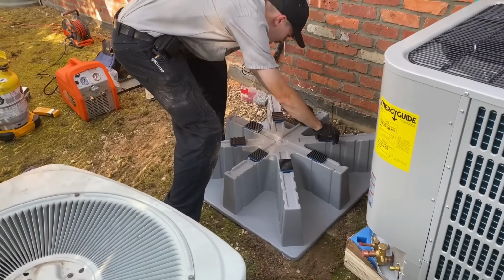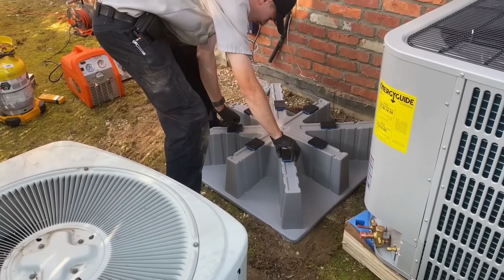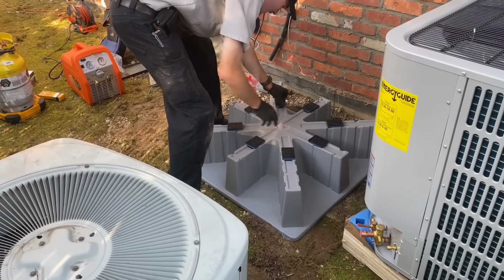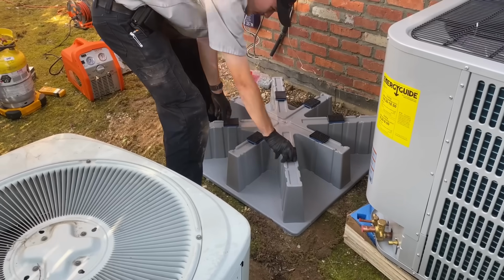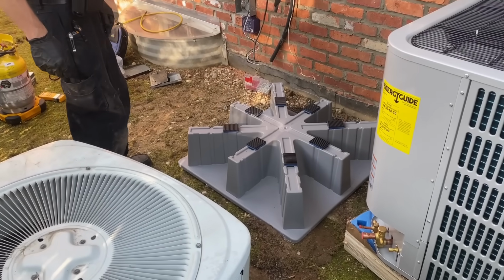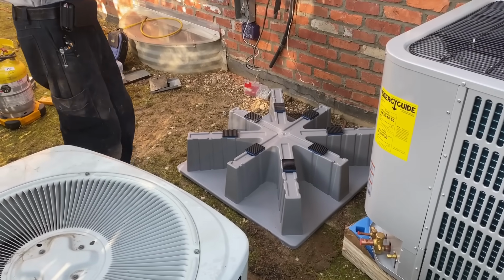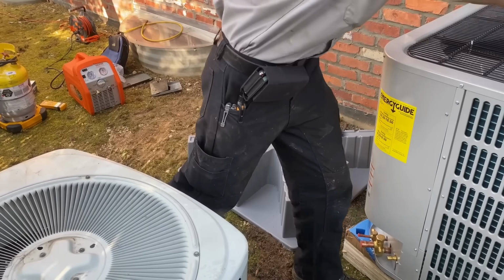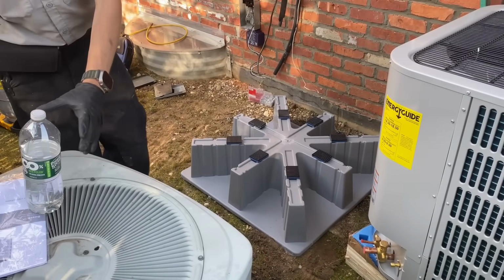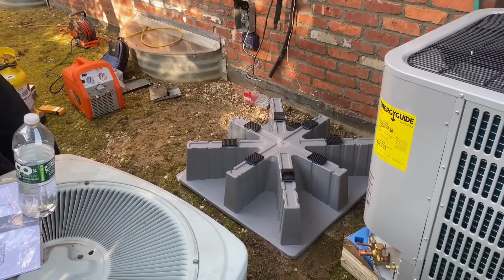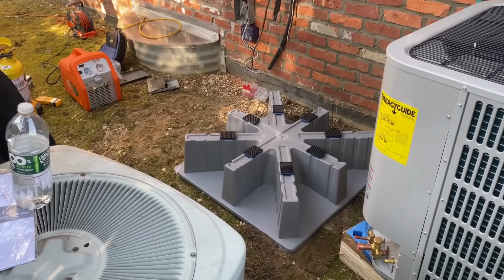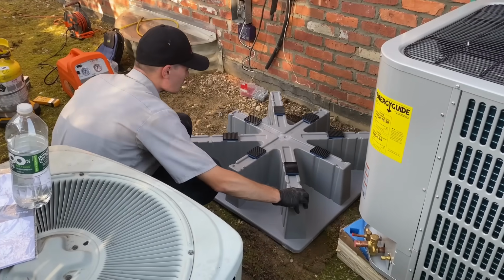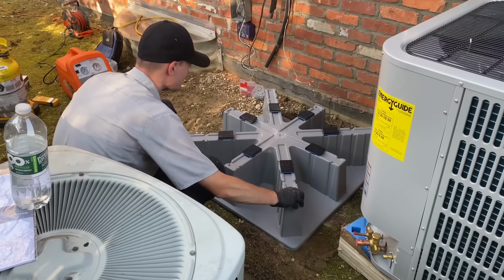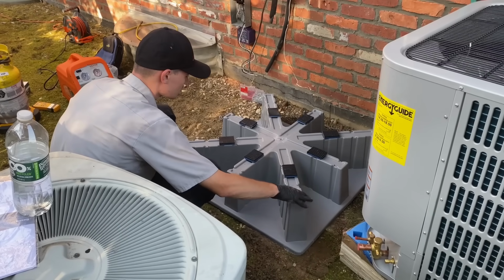So right now, Daniel is setting the heat pump riser outdoor unit pad. We keep them elevated because in the winter months, condensation will be forming outside, and you don't want that to freeze and the unit turn into an iceberg. So we keep it elevated. I'm using this pad by Diversitech. It's an awesome pad. It's not recommended in the manual, doesn't specify that, but...